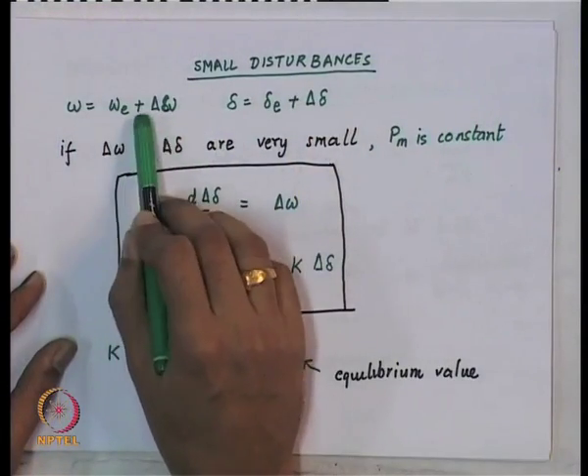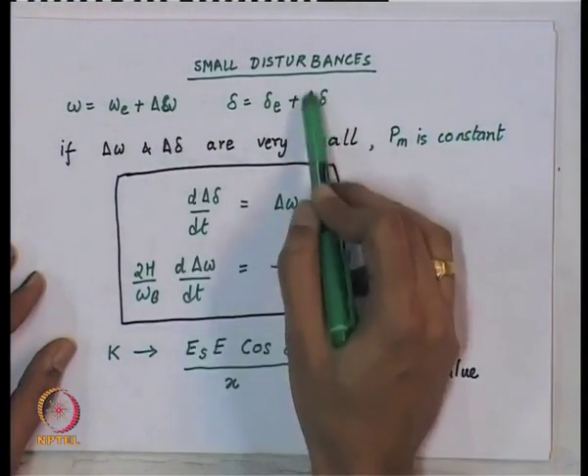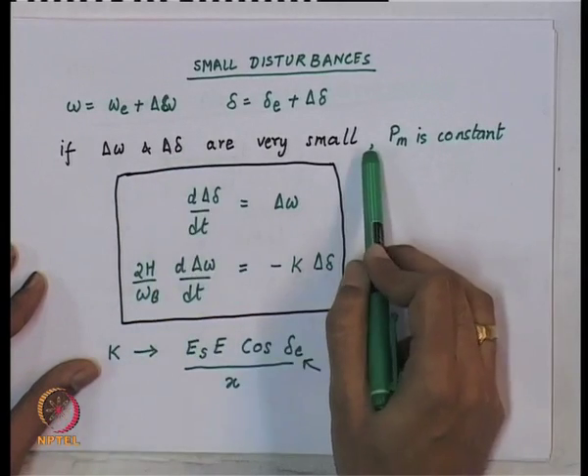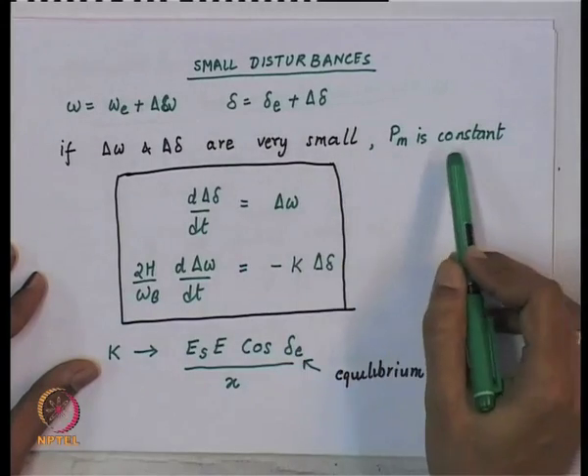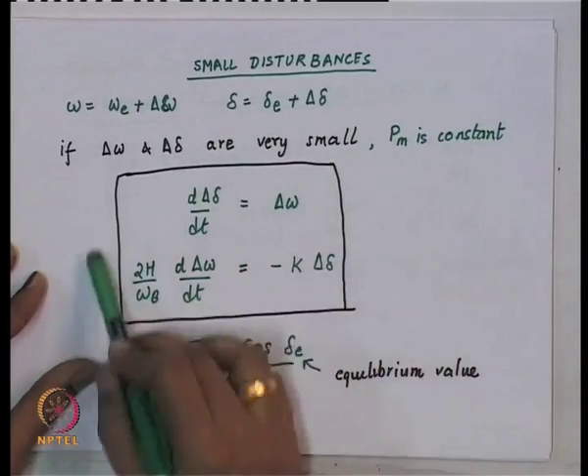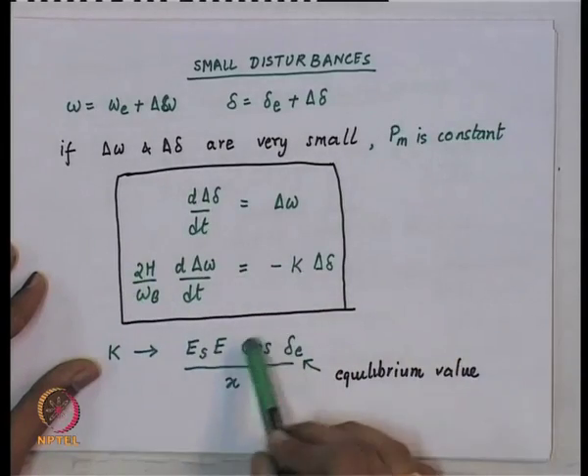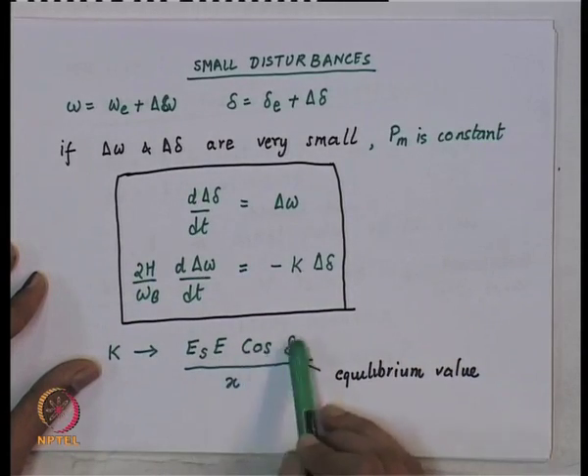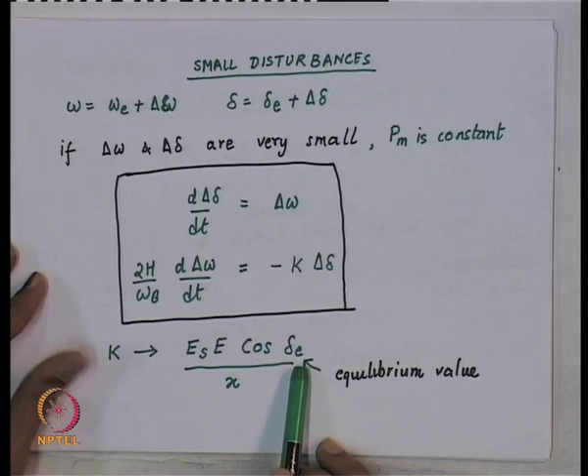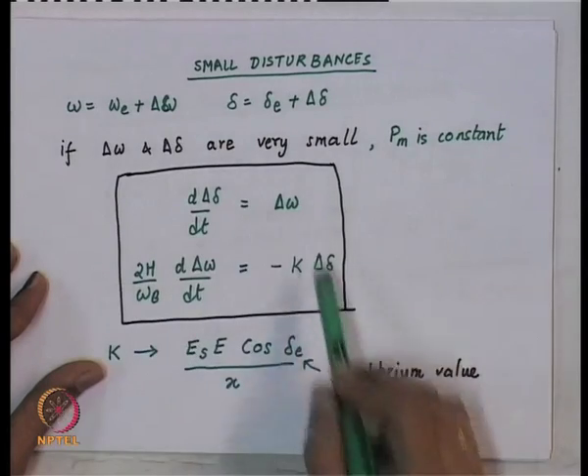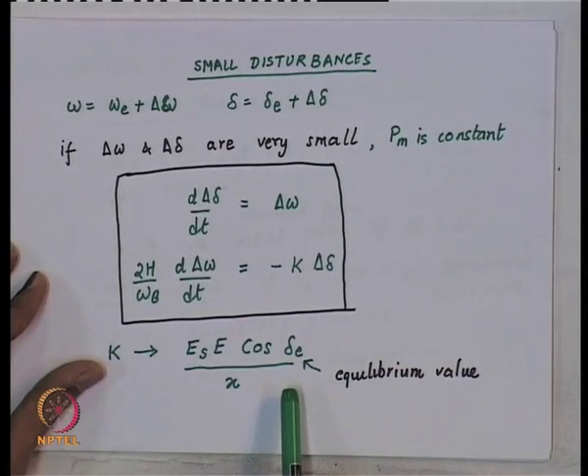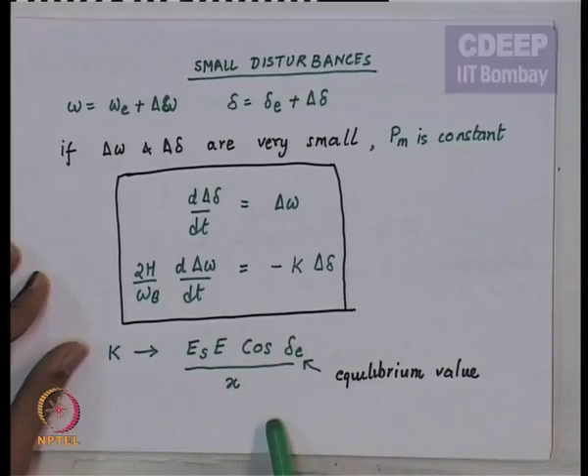Looking again at what we did: we assumed small deviations around the equilibrium, so delta-omega and delta-delta are very small. P_m is a constant. We obtained a linearized model where k was E_s·E·cos(delta_e)/x, where delta_e is the equilibrium value. So if you are studying deviations around an equilibrium (delta_e, omega_e), then k would be this. After that, we obtained the response for small disturbances.